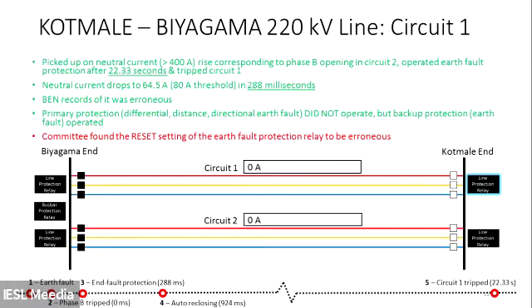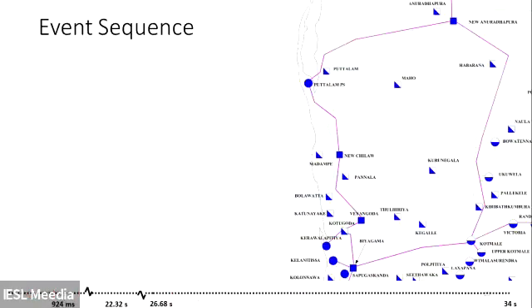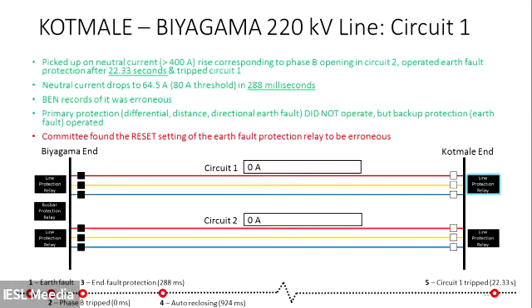So there is a question as to why this earth fault protection operated when the current is below the threshold. This is our committee's finding, and CEB may have different opinions on that. We found that the reset setting of the relay was erroneous. We will come to the details in a while. That is what we felt as the committee. These are the main two events which triggered the whole failure on the 3rd of December.